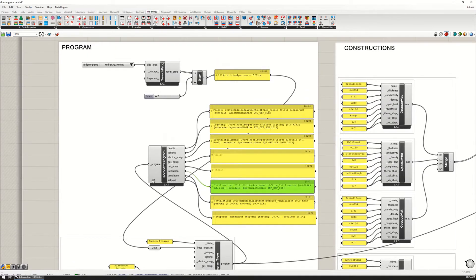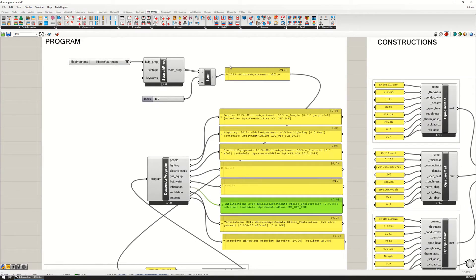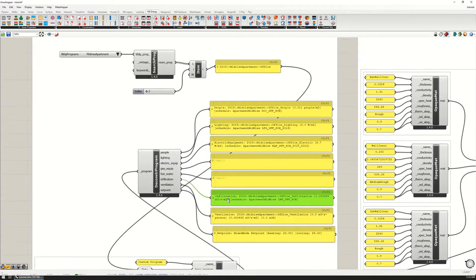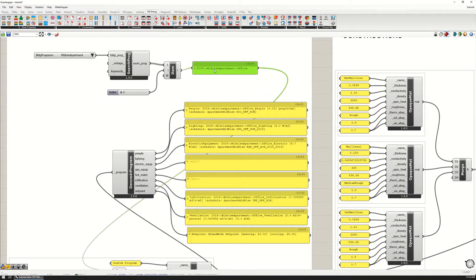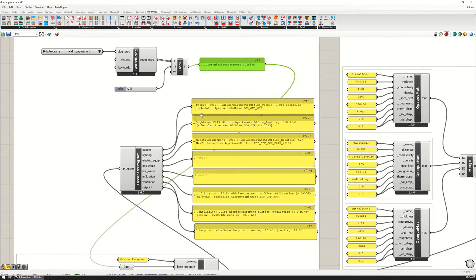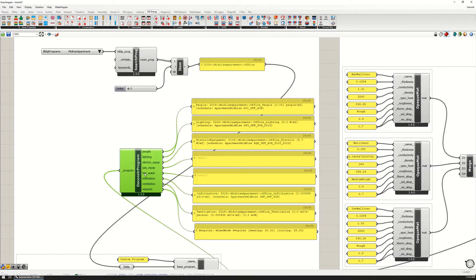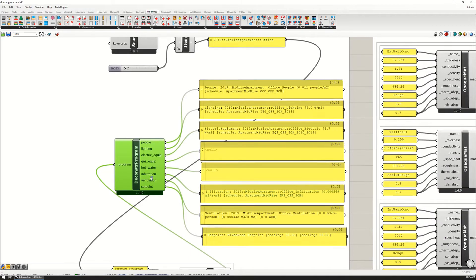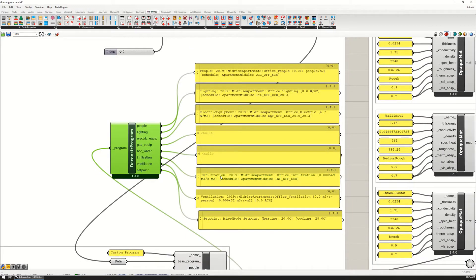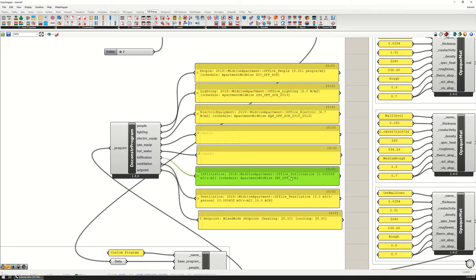How infiltration and ventilation affect your model: if you look at the program, every specific program that is preset in Honeybee is associated with a set of infiltration and ventilation. The infiltration for this mid-rise apartment office is set to 0.0005 cubic meters per second per square meter.